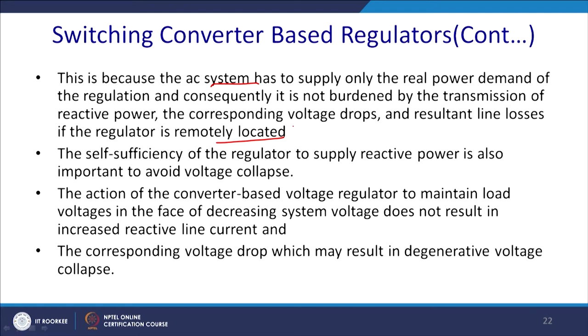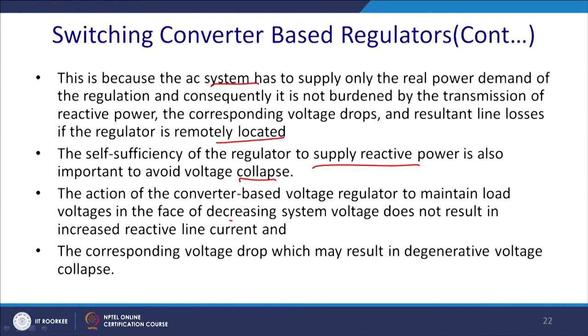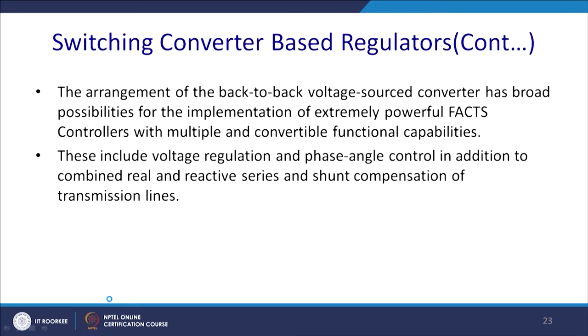The capability of the regulator to supply reactive power is also important to avoid voltage collapse. So that is something, it has a self-healing mechanism. The action of the converter-based voltage regulator to maintain the load voltage in the face of decreasing system voltage does not result in increased reactive line current. The corresponding voltage drop, which may result in degenerative voltage collapse, is something we require to take care of. For this reason, the arrangement of the back-to-back voltage source converter has broad possibilities of implementation of an extremely powerful FACTS controller, with multiple convertible functional capabilities.